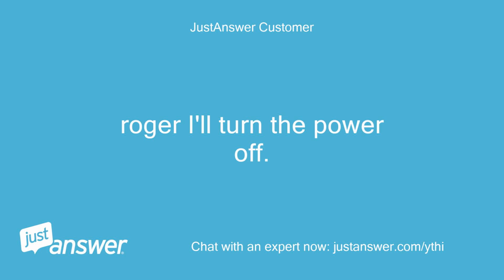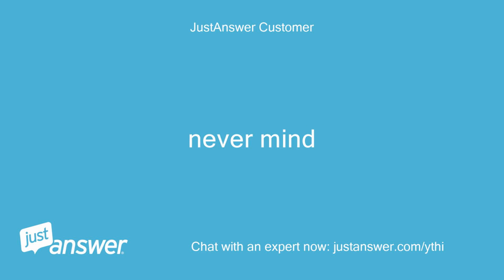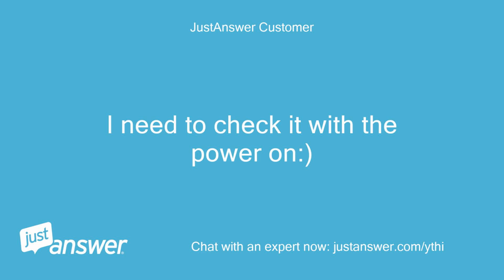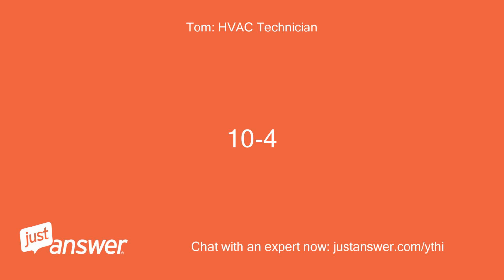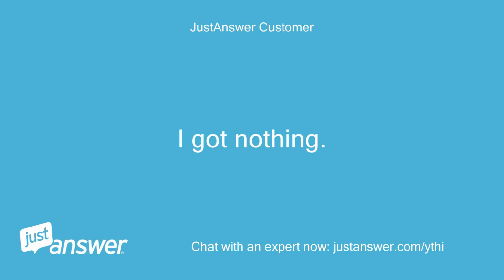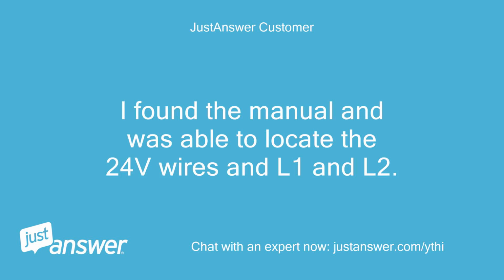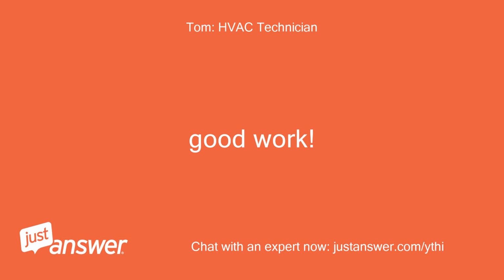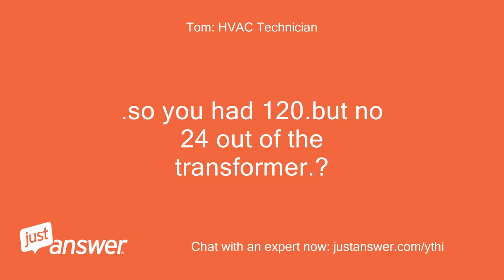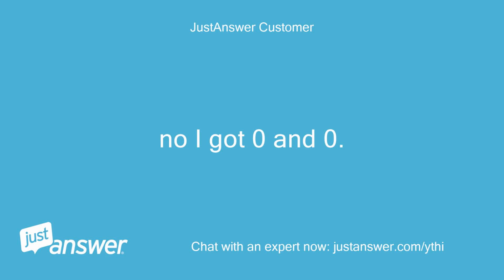Roger. I'll turn the power off. Never mind. I need to check it with the power on. 10-4. Okay. I got nothing. I found the manual and was able to locate the 24 volts wires and L1 and L2. Good work. So you had 120. But no 24 out of the transformer. No, I got 0 and 0.